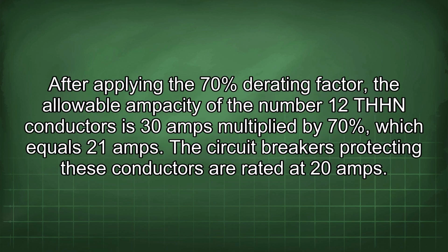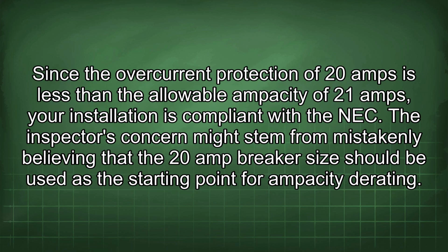After applying the 70% derating factor, the allowable ampacity of the number 12 THHN conductors is 30 amps multiplied by 70%, which equals 21 amps. The circuit breakers protecting these conductors are rated at 20 amps. Since the overcurrent protection of 20 amps is less than the allowable ampacity of 21 amps, your installation is compliant with the NEC. The inspector's concern might stem from mistakenly believing that the 20 amp breaker size should be used as the starting point for ampacity derating.